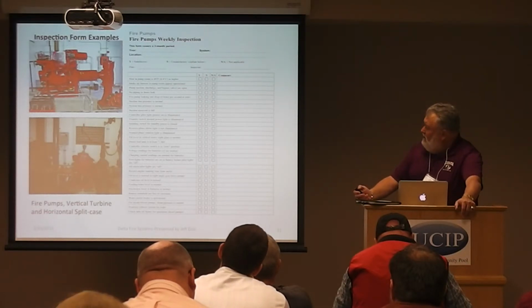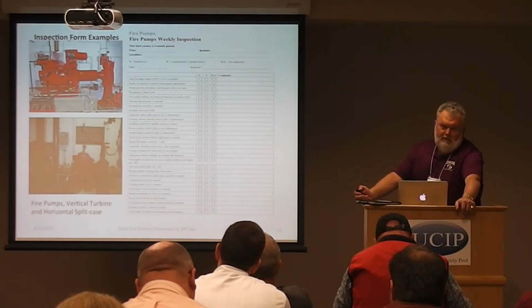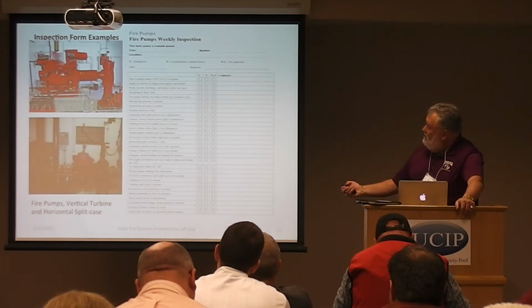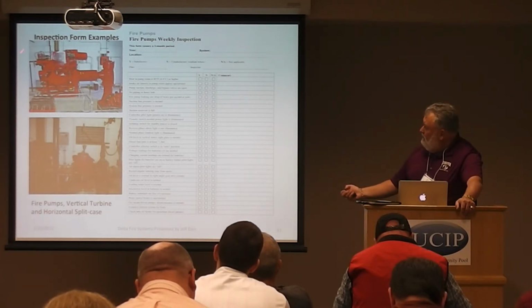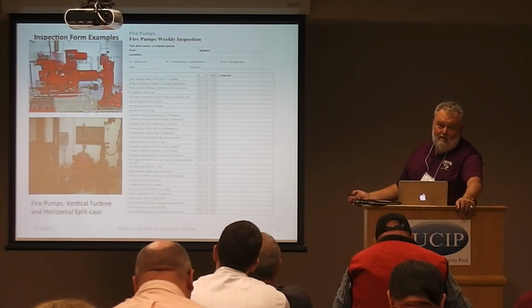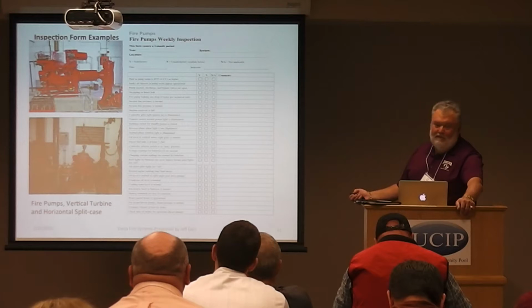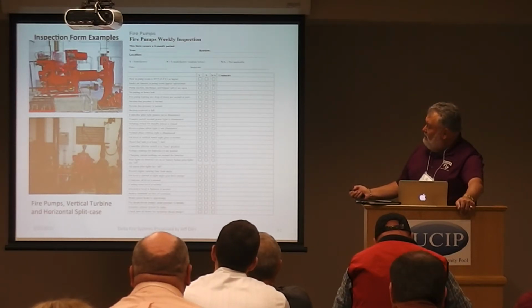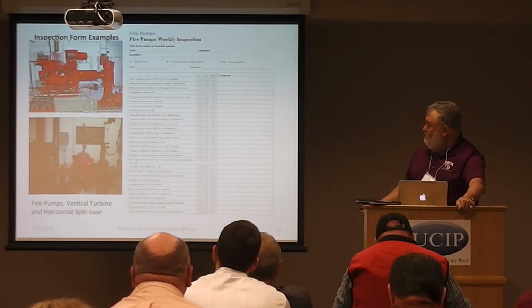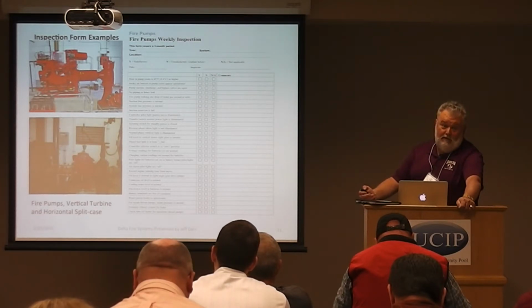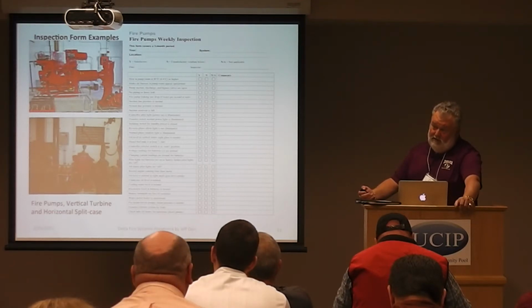Fire pumps. Basically 2 separate types of fire pumps here. This top one being a vertical turbine diesel pump. This house is built on top of an underground storage tank, so that's pulling water up with the diesel pump itself. This is a horizontal split case pump. This is an electric pump here. Both of these are quite common in buildings, not so much in Utah, but other parts of the country.